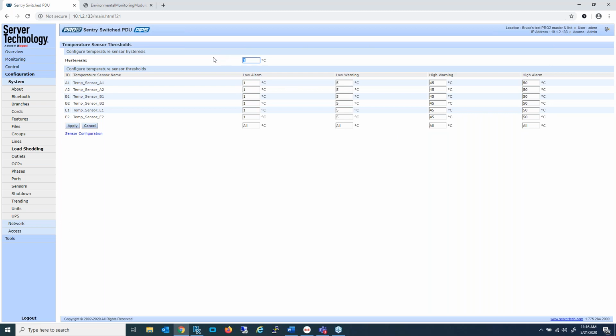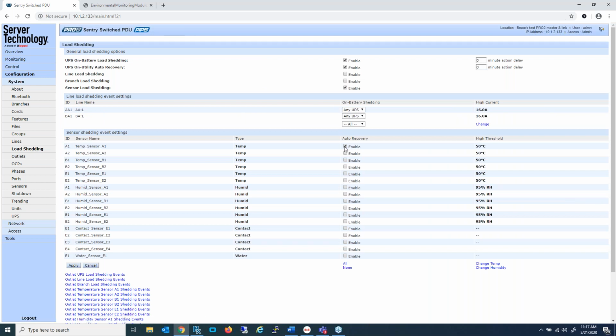There is a hysteresis. What that means, at least as configured today, is that the high alarm threshold is what triggers a load shedding event. If the temperature exceeded 50 degrees Celsius, the load shedding event would occur, and the temperature would have to drop down to 49 degrees Celsius in order for the outlet to automatically switch back on. And that would only be if auto recovery was enabled. I previously enabled that feature.